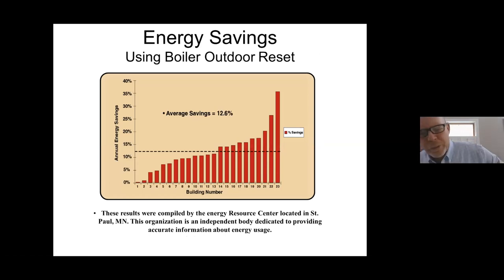A few years ago, a study was compiled by the Energy Resource Center in St. Paul, Minnesota. They asked Tekmar for 23 single-stage boiler reset controls and applied them to 23 boiler rooms throughout St. Paul. On average between the buildings, it was about 12.5% fuel savings. Some buildings experienced very little savings; some were quite extreme. But on average, it was around 12 to 12.5%. That study is available on Tekmar's website if anyone is interested in reading about how they conducted it and the final results.